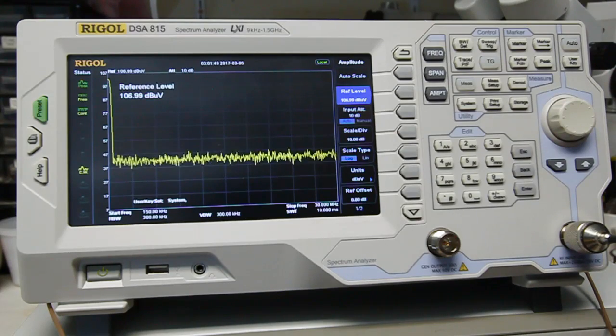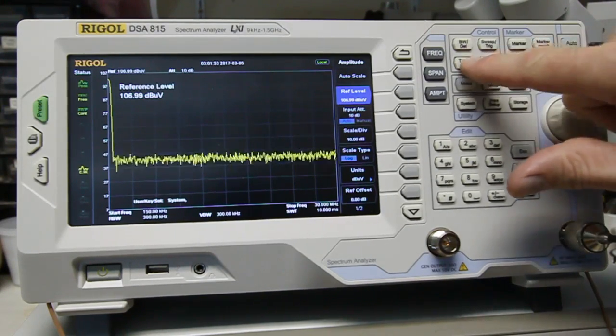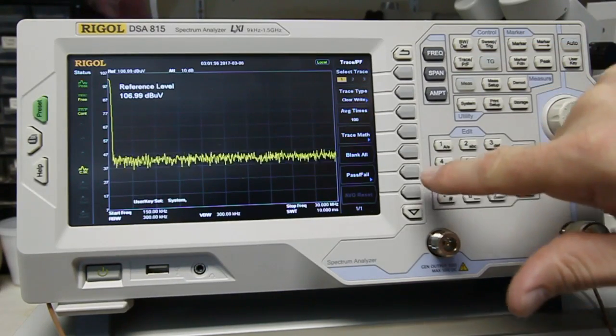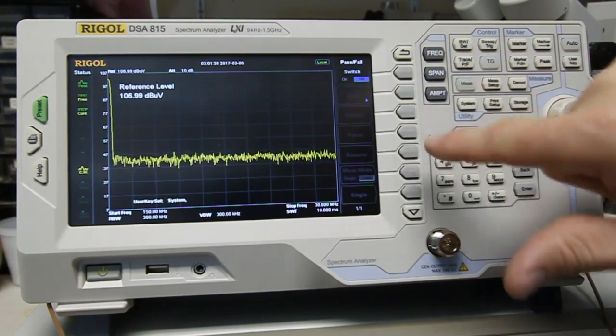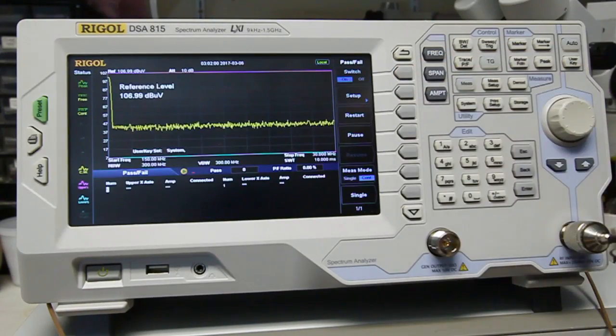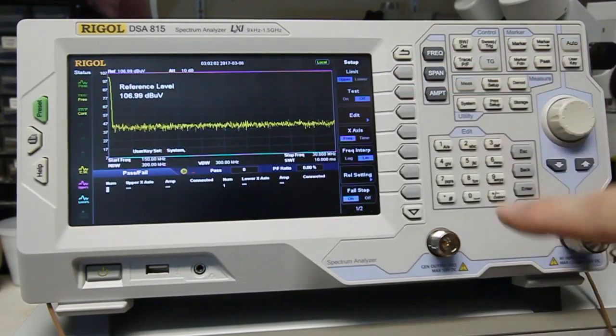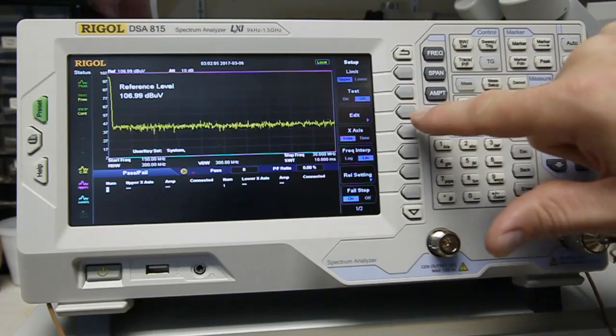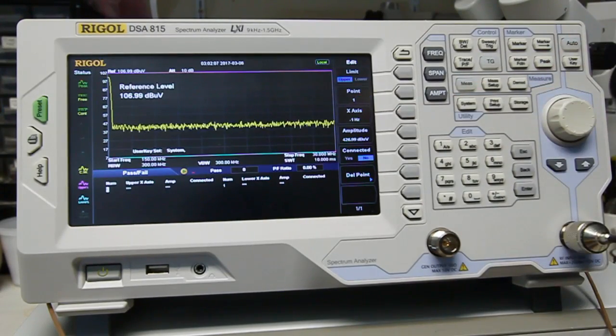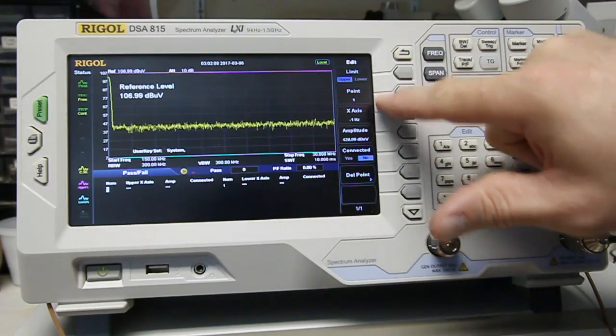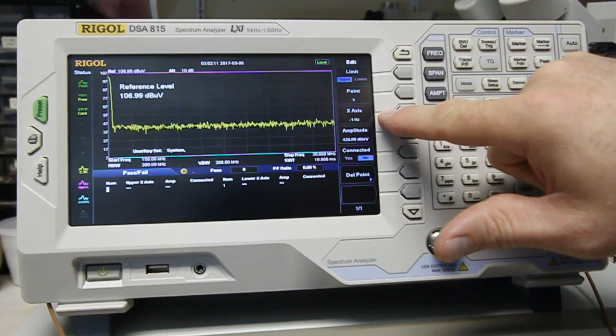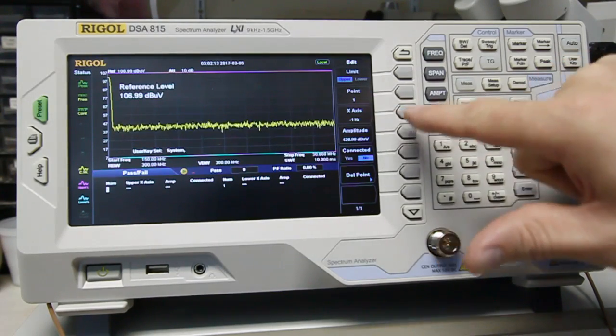First thing I'm going to do is I'm going to set up the limit lines. So I'm going to go into trace pass fail, turn it on. I'm going to go to setup, edit. So we're going to enter in our first point and we're going to enter in the frequency of our first point. That's the 150 kilohertz.